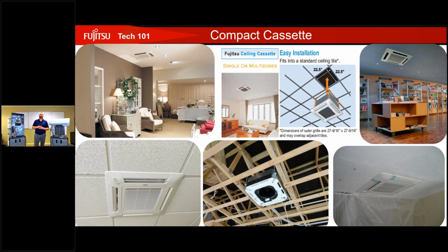Left-hand side, that's going to be your most basic install with this unit. That's where you're going to see it the most. As you can see in the middle bottom photo there, we are nice and snug to the ceiling, hung with threaded rod. That's really basically the perfect installation there.